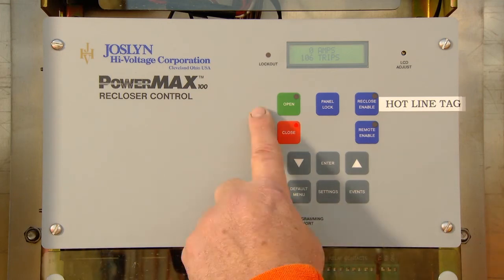Open. Pressing this button with the recloser closed will cause the control to open the recloser and go to lockout. When the recloser is open, the green LED will be illuminated. When the control is in lockout, the yellow lockout LED will be illuminated.